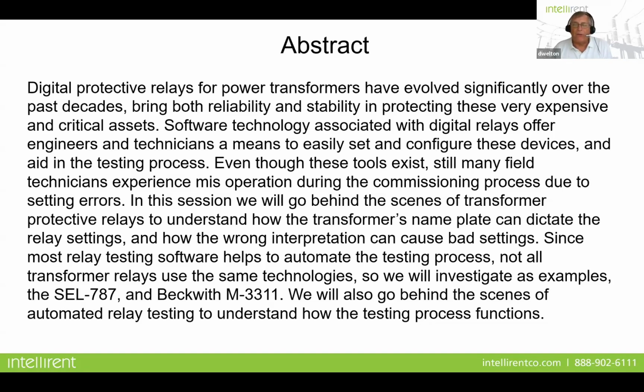So I came up with this presentation for a number of reasons, and I think our last speaker talked a lot about reliability. Reliability in the protective relaying world means that the relay does what it's supposed to do in the event of a fault or some type of event that would activate the relay to give a response. The other half of that is called security. Security means that in the relay world we're not going to trip when we're not supposed to. So there are two important terms that we have to consider when we talk about protective relaying.